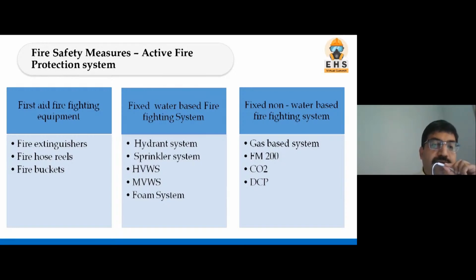Now coming to the fixed water-based equipment, what is that? The hydrant system is there, and the sprinkler system is there. There is high velocity water spray for transformers, medium velocity water spray for big flammable tanks, and foam systems. These are water-based systems, where water is used. Non-water-based means where water is not used, for example a CO2 system. In the server room, you must have heard about FM200, which gets flooded in case of fire, or inert gases, which we are using nowadays. All those are non-water-based systems.